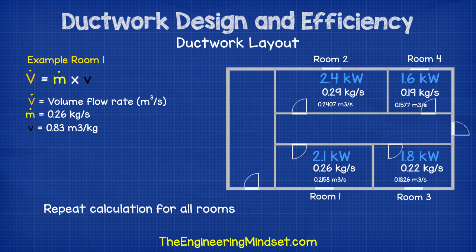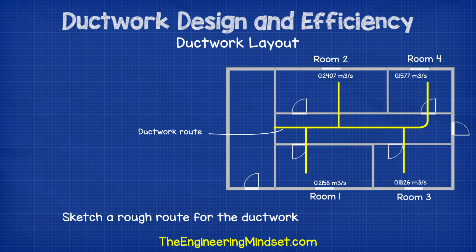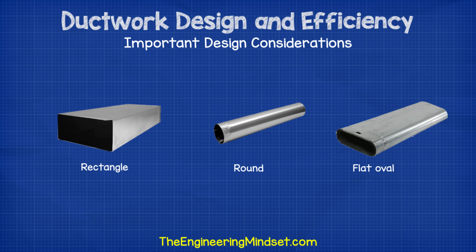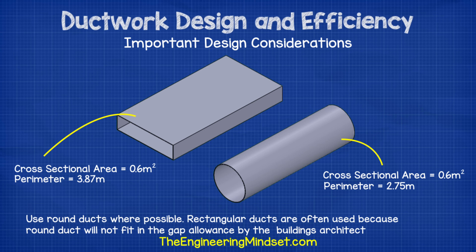Now we're going to sketch out our ductwork route onto the floor plan so we can start to size it. Before we size that, we need to consider some things which will play a big role in the overall efficiency of the system. The first point is the shape of the ductwork. Ductwork comes in round, rectangular, and flat oval shape. Round duct is by far the most energy efficient type, and that's what we're going to use in our worked example. A round duct with a cross-sectional area of 0.6 meters squared has a perimeter of 2.75 meters, whereas a rectangular duct with equal cross-sectional area has a perimeter of 3.87 meters. The rectangular duct therefore requires more metal, adding more weight and cost. The larger perimeter also means more air contact with the material, adding friction. Friction means a fan needs to work harder, resulting in higher operating costs. Always use round duct where possible.